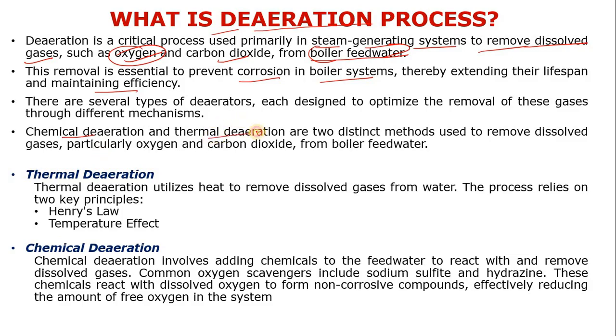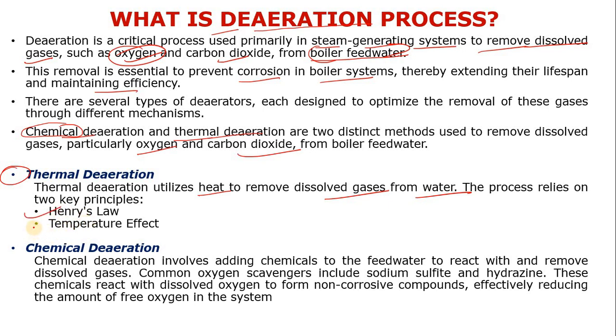There are two main types of de-aeration processes used in a plant: chemical de-aeration and thermal de-aeration. In thermal de-aeration you use heat, and in chemical de-aeration you use chemicals to enhance the de-aeration process. Both are distinct methods to remove dissolved gases — particularly oxygen and carbon dioxide — from the feed water. Thermal de-aeration utilizes heat and relies on two key principles: Henry's Law and the temperature effect.